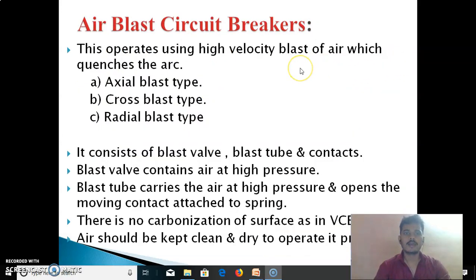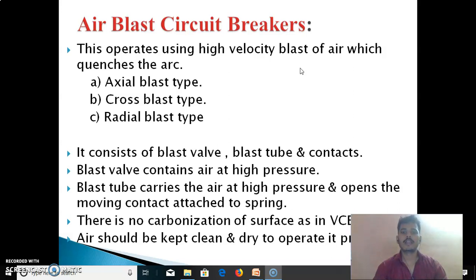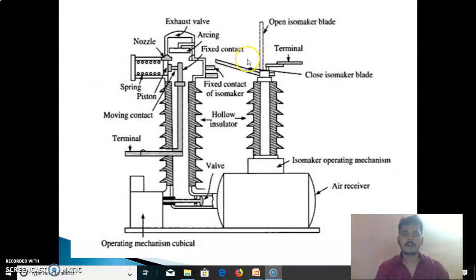Next, we see the air blast circuit breaker. This operates using high velocity blasts of air which quench the arc. There are three types: axial blast type, cross blast type, and radial blast type. It consists of a blast wall, blast tube, and contacts. The blast valve contains air at high pressure. The blast tube carries air at high pressure and opens the moving contact attached to a spring. There is no carbonization of surfaces as in a vacuum circuit breaker. Air should be kept clean and dry to operate it properly. In the diagram, there is the fixed contact, moving contact, spring, piston, nozzle, exhaust valve, arcing, fixed contact of the isolator, hollow insulator, valve, air receiver, and open isolator blade.